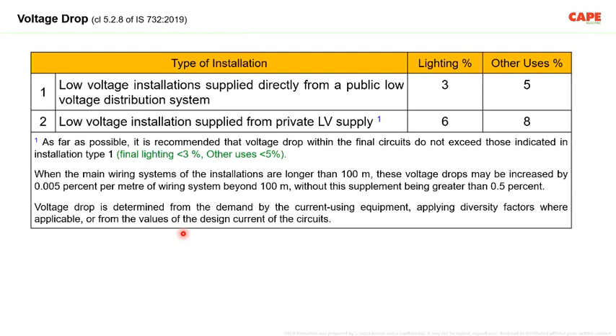Similarly, voltage drop. The maximum voltage drop inside a consumer premise is set by the standard. A lot of engineers interpret that for a lighting load in case of a public electricity supply it is only 3%, and even if it is 4, 5, 6%, nothing happens. This is what people think. In case of a low voltage supply from our own transformer, up to 6% voltage drop is allowed for lighting load. But people sometimes interpret that even if it is 7 or 8%, my lights are able to work, because my light works with 230 plus or minus 20%, for example. As a result, people do not take these requirements seriously.